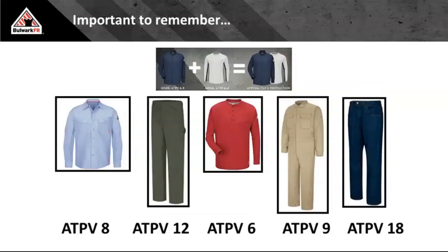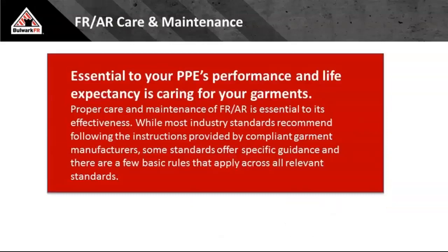But remember what I told you, what else you are wearing factors into what you can do. Just because from the waist up you're 24 does not automatically allow you to do 24 work. If your lower half is 12, your upper half is 24, and assuming your hard hat, face shield, and balaclava are all dialed in, and 12 is your lowest number, guess what? You work on 12 or lower gear. 9, if you're wearing a base layer underneath that coverall and you are skivvies from the waist down, guess what? You're doing 9 work. So hopefully that makes sense. Make sure you research your layerings, but there are some key advantages to it.